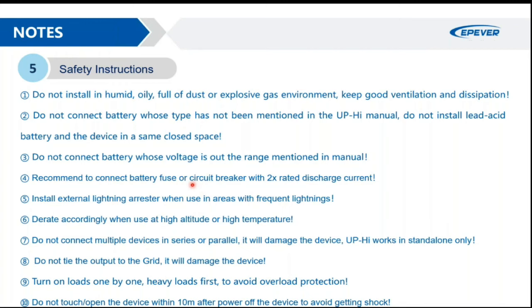Recommend to connect battery fuse or circuit breaker with 2 times higher than the rated discharge current. Install external lightning arrestor. I would recommend always, not only when it's prone to lightning. As an off-grid user, you should always be ready for transients, like peaks in voltage, peaks in current, lightning, and whatever. You should be prepared for that. And trust me, that is much cheaper than getting a device damaged because of the transients. And you need to rate your power according to the criteria that I told you. Only 50% capacity would suffice.